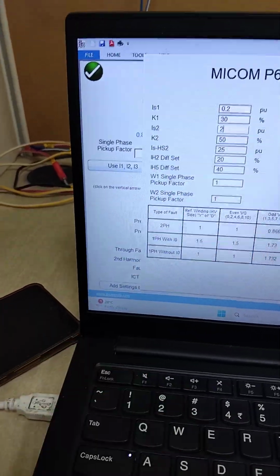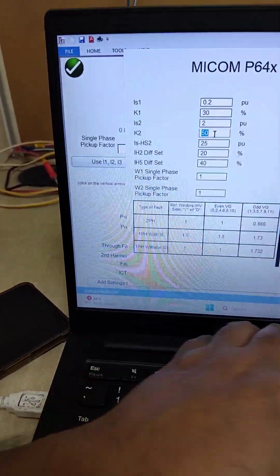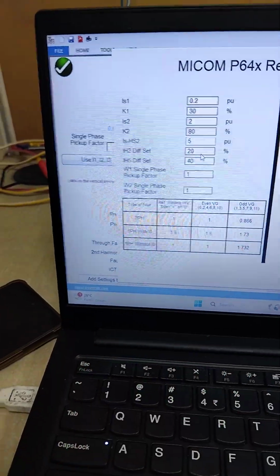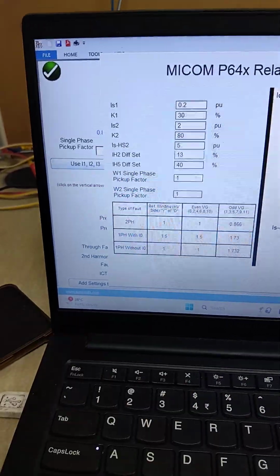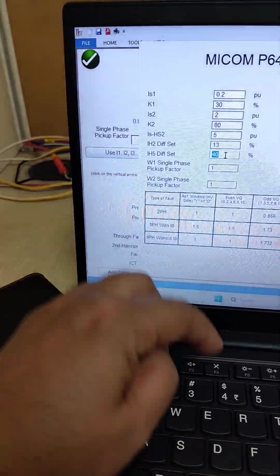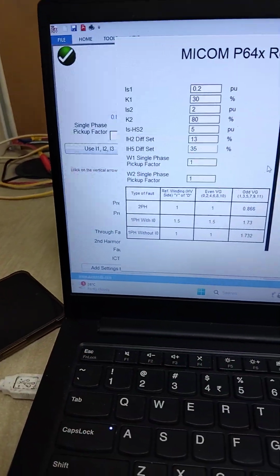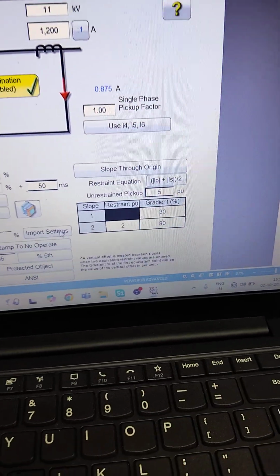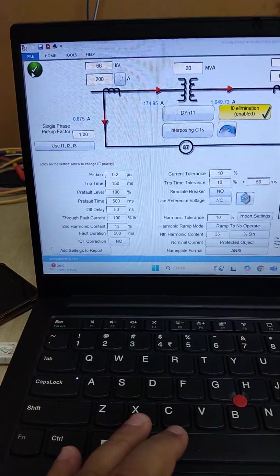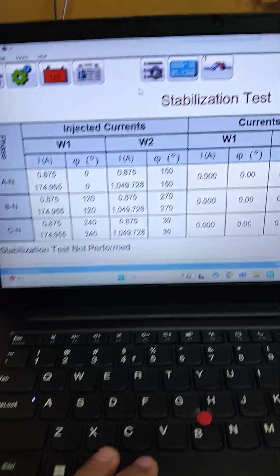Cut point is 2. Then K2 is 80%. Then high set is 5. This is 13. Second harmonic blocking and fifth harmonic blocking is 35. Choose these values, select, and you can see the settings have already been updated in the device. Now check OK, and you can see all the test tabs will appear here.